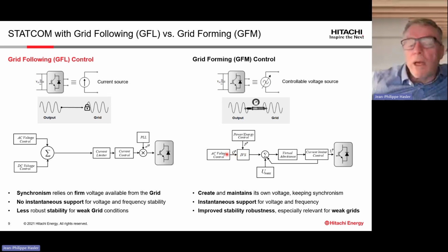It is the same way when we have a voltage control: we want to change the magnitude of this voltage, not fast, for sure, using the voltage control. And you can see in this scheme, we are now controlling power and reactive power, P and Q. We are not controlling any current, which was, say, expressed in the past in the dq system, having a reference of the PLL. And now we don't have any PLL at all.